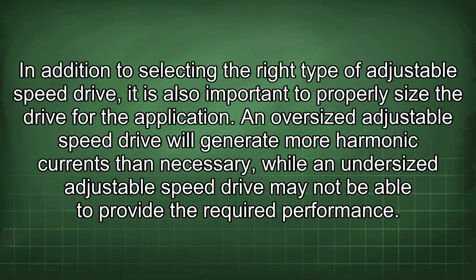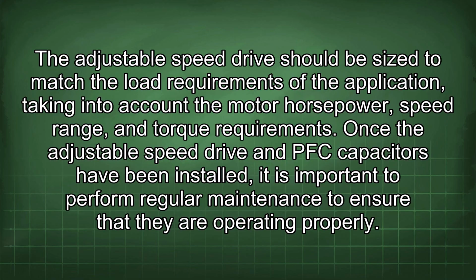In addition to selecting the right type of adjustable speed drive, it is also important to properly size the drive for the application. An oversized adjustable speed drive will generate more harmonic currents than necessary, while an undersized adjustable speed drive may not be able to provide the required performance. The adjustable speed drive should be sized to match the load requirements of the application, taking into account the motor horsepower, speed range, and torque requirements.